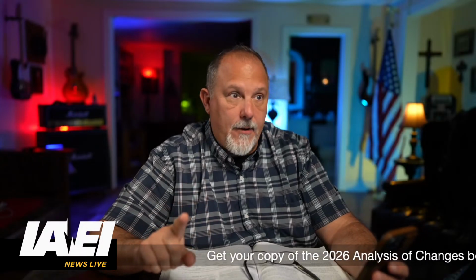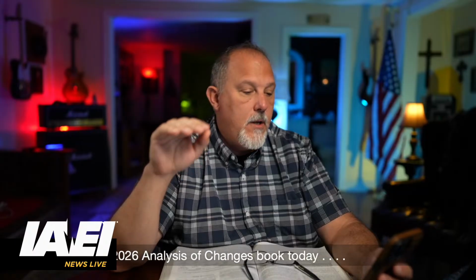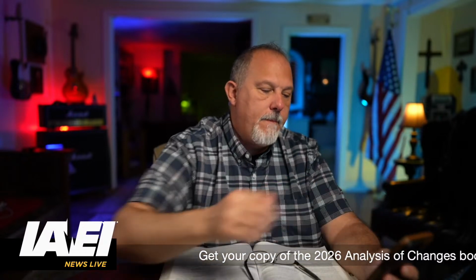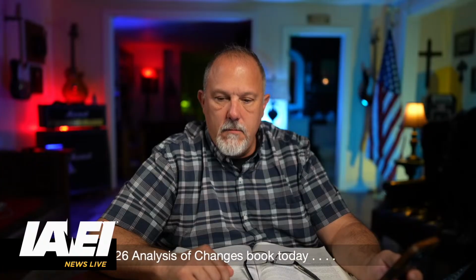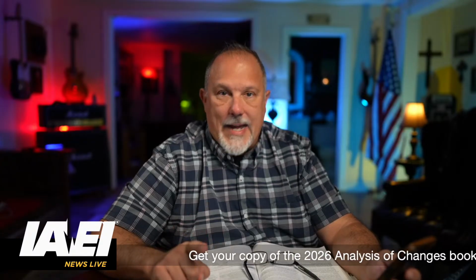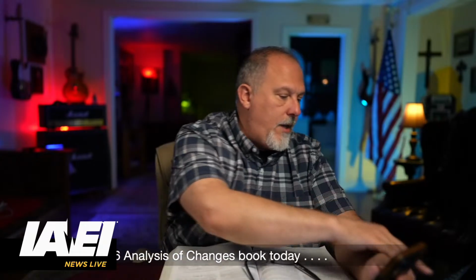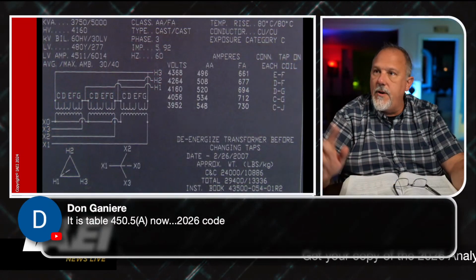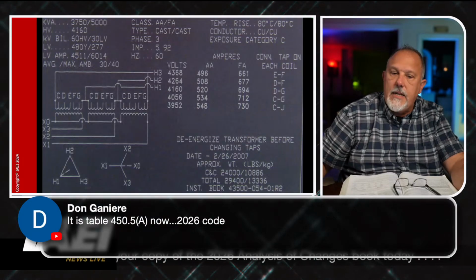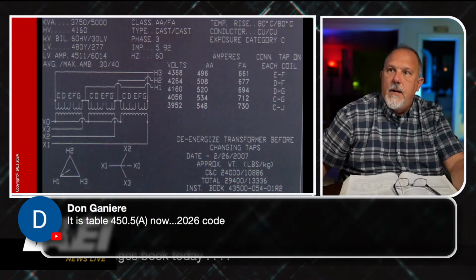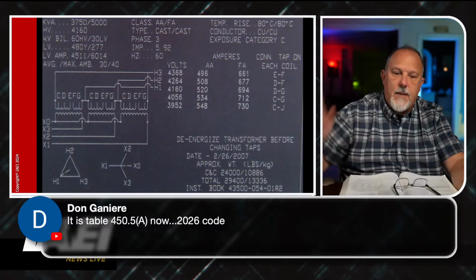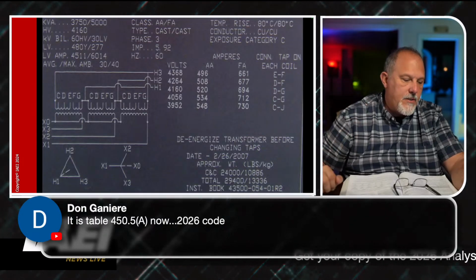Okay, and then on the secondary, since I'm not more than 6%, on the secondary, I have 300% for a breaker, 250% for a fuse if it's over 1,000 volts. If it's, say, in this case here, we're at 480 volts on the secondary, and I know that because of right here.